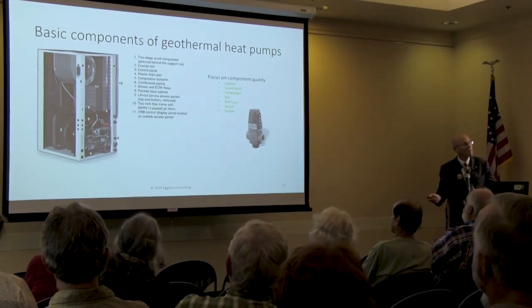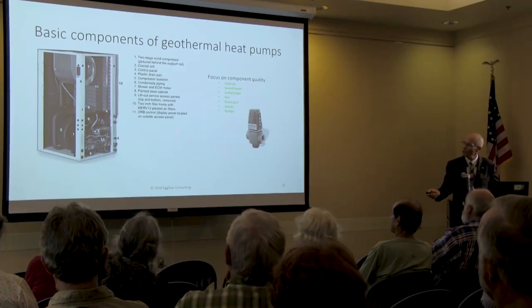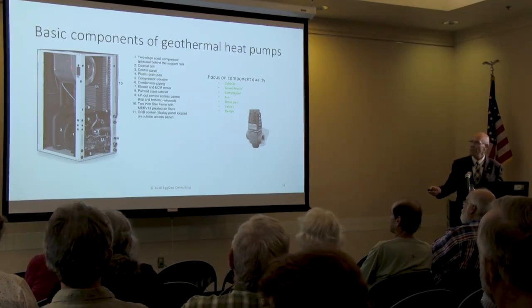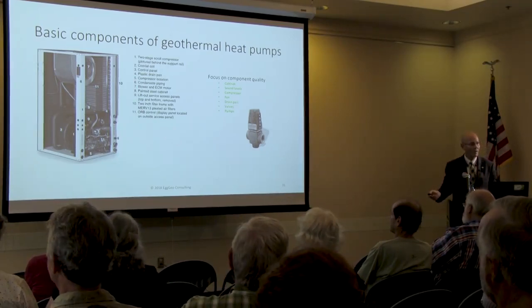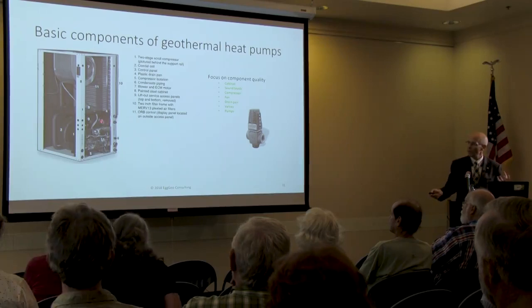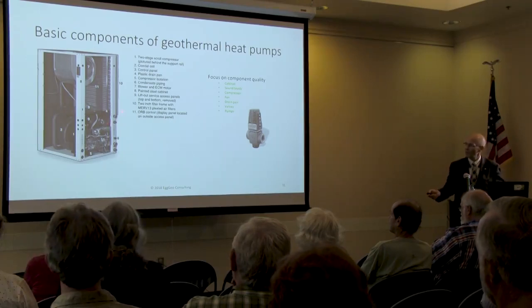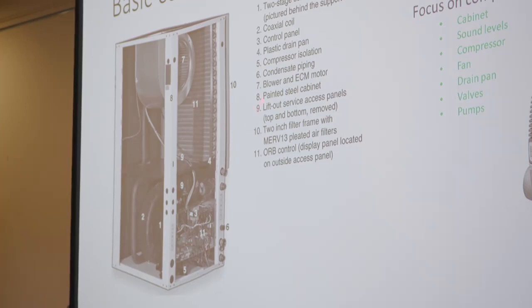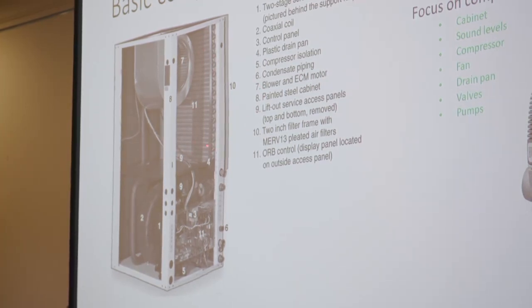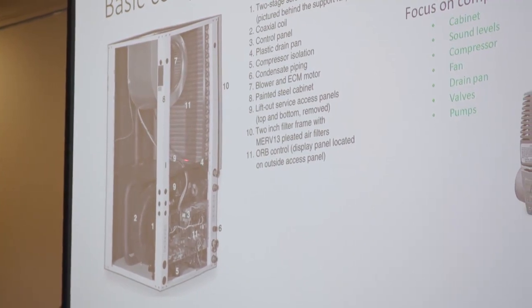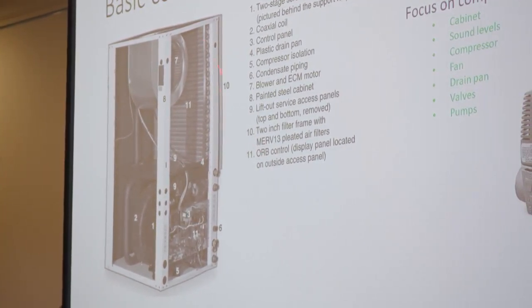This is a basic garden variety geothermal heat pump. Just so you realize, you have a fan. This is a water-to-air heat pump, by the way. There are water-to-water, which I have a description of coming up soon. But you have a fan, you have a coil here that transfers heat with the air stream. This is either the heating coil in the heating mode or the cooling coil in the cooling mode. And the fan draws air through it, and it goes up into a duct system.